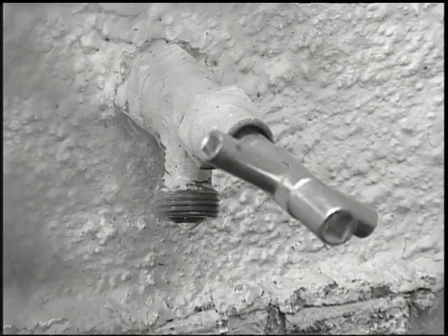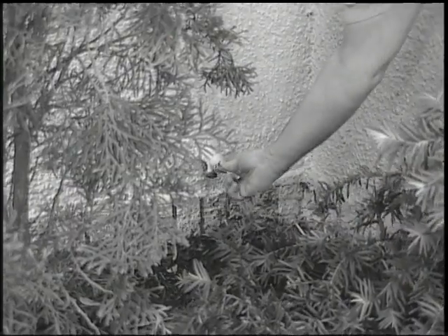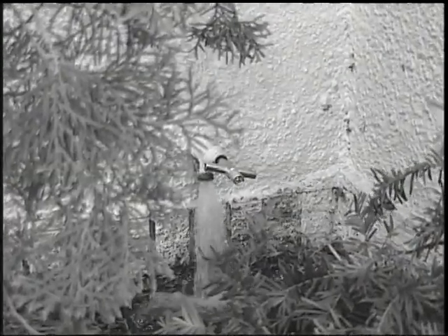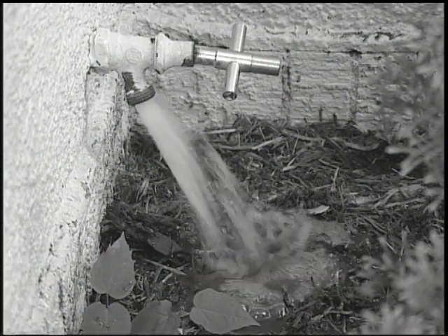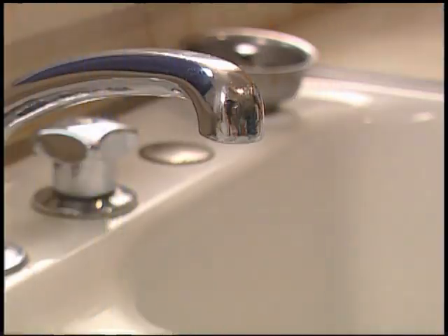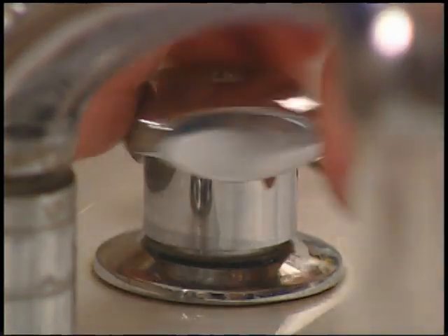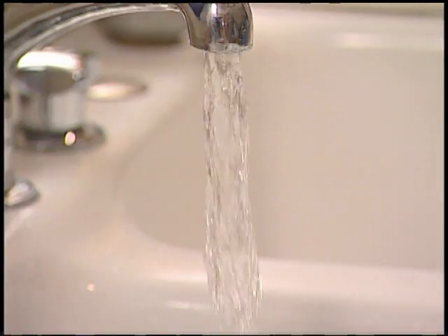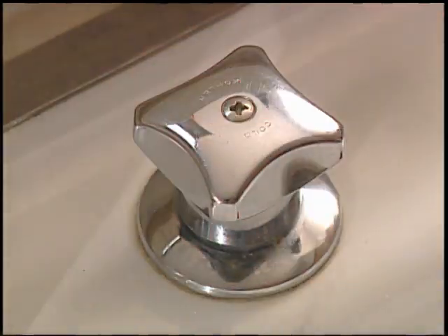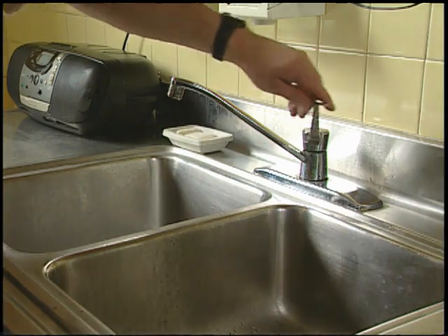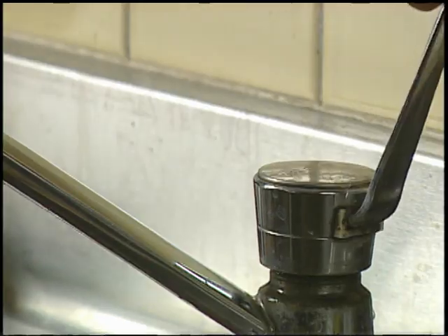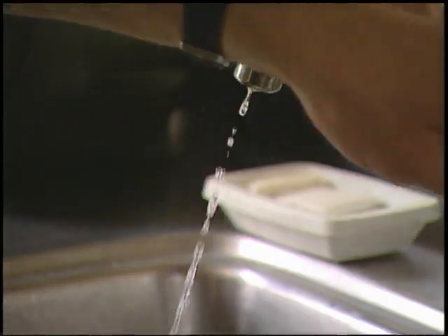Sampling faucets should not be located near the ground and, if possible, should be inside a residence or building to avoid environmental contamination. Faucets utilizing separate controls for the hot and cold water should be chosen, with only the cold water tap used for sampling. Faucets that use a single lever controller for both the hot and cold water should not be used.